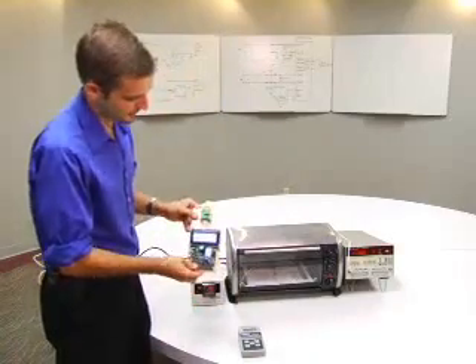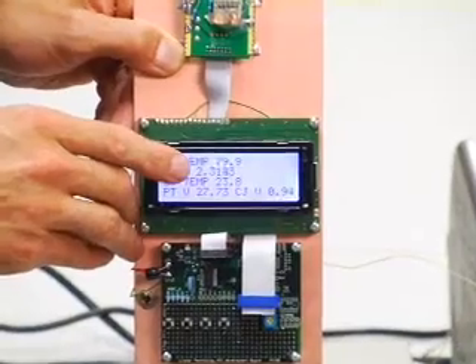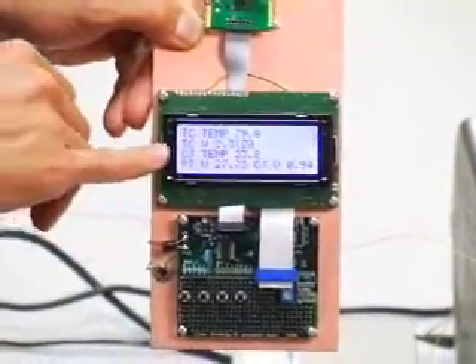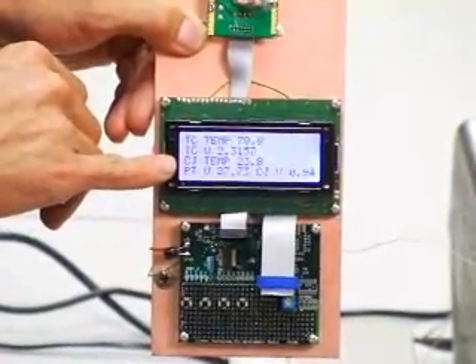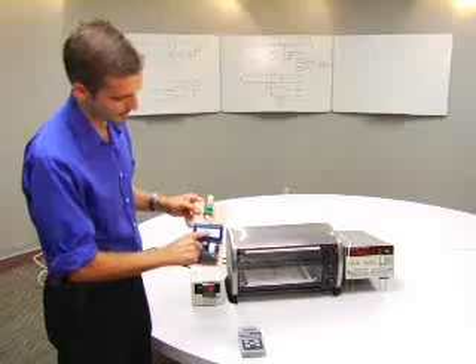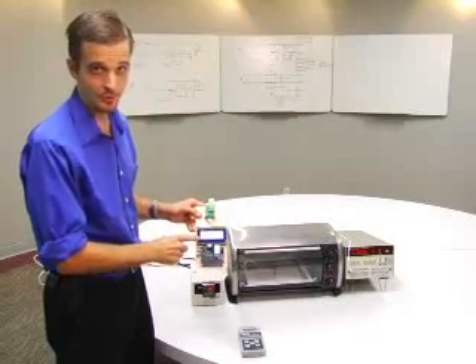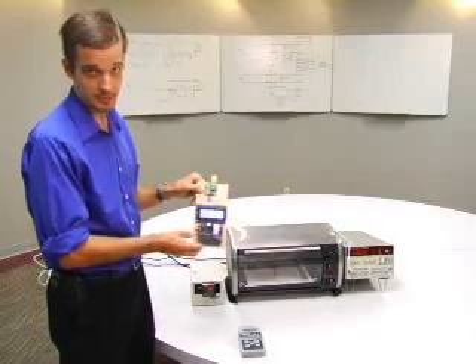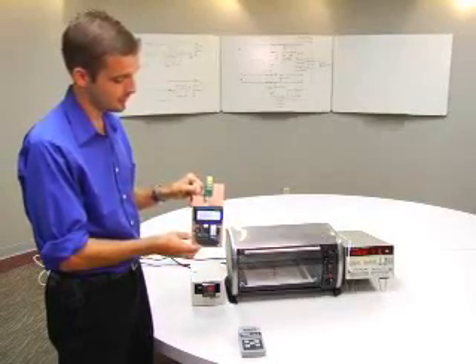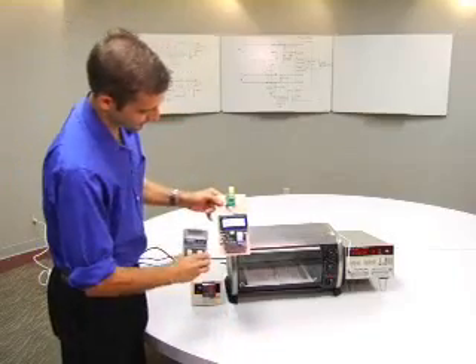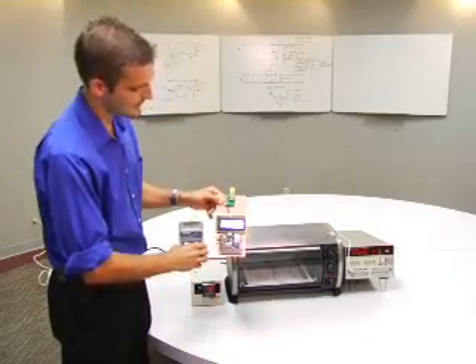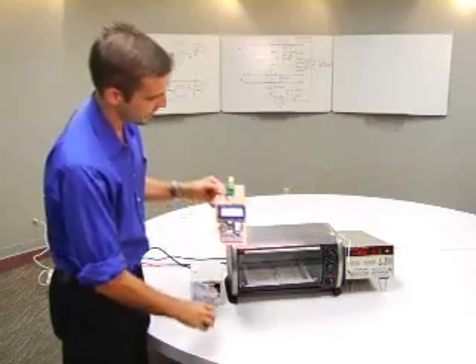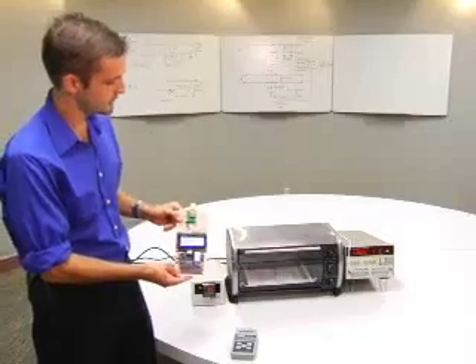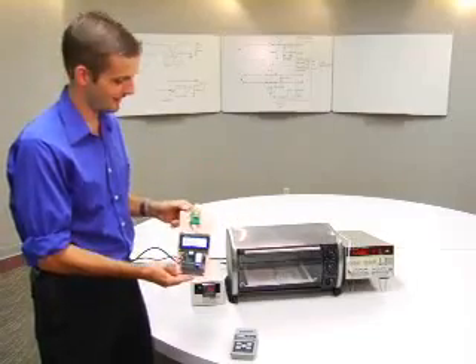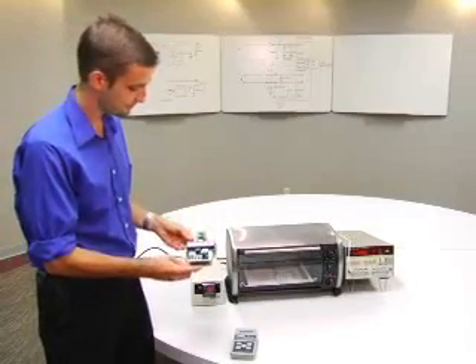So let's look at a few of the numbers here. So the calculated thermocouple temperature is about 79.9 or 80.1 degrees. We've got a couple tenths of a degree of flicker, which is about what you would expect given the 600 nanovolt noise of the A to D converter itself, which compares quite well to the 79.8 degrees read on the commercial meter. And we're still a couple degrees off from the quartz thermometer. It's different sensors, and this is not exactly a first-class calibration setup.